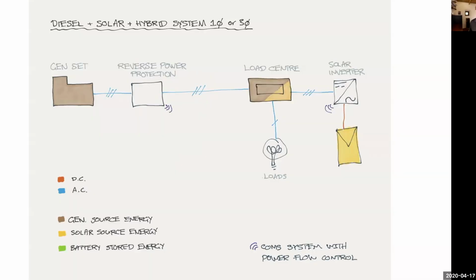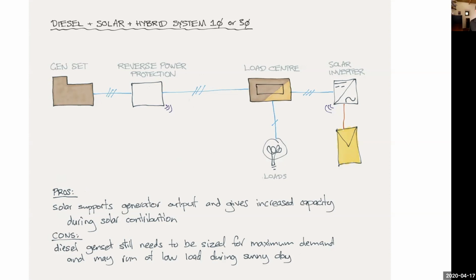So let me jump back into my presentation. We talked about a batteryless system where we've basically got an off-grid site, probably a commercial or industrial site that runs a generating set continuously. The pros are that solar helps support the generator's output, so the main benefit may be that peak demand correlates with the sun. You may have heavy daytime loads, and the generating set can be somewhat undersized as long as that solar is fairly reliable, so not a coastal area where clouds come in all the time. But the cons are that you reduce demand on the gen set, where fuel consumption might be poor. So unless you've got a low-load designed generating set, too much renewables in this situation can lead to poor fuel efficiency on that generating set.